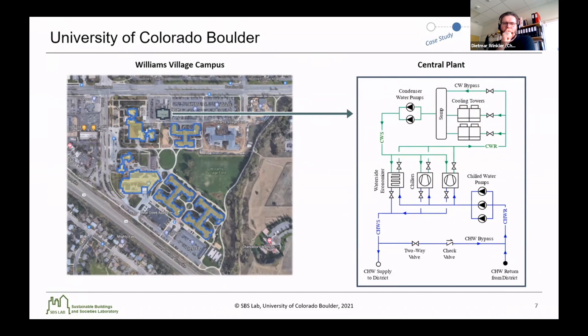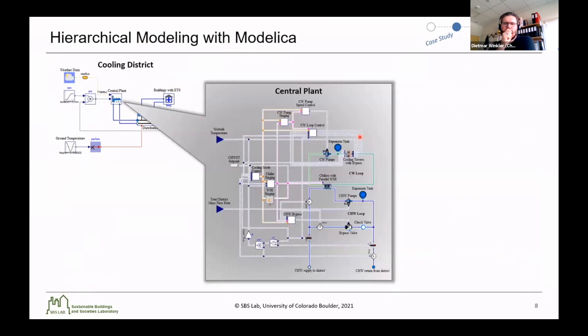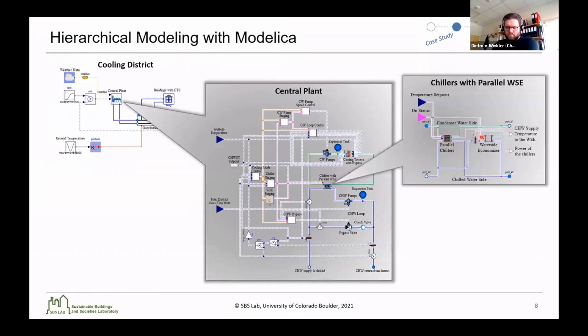This district cooling system was implemented in Modelica. The top-level Modelica diagram shows the model was built hierarchically, allowing each subsystem and building to be tested in isolation and various configurations to be tested as well. At this top level, we have a central plant, a distribution network, and a vectorized set of buildings representing each of the six buildings. Unpacking the central plant, you can see the schematic of the fluid loops with both the condenser water loops and chilled water loops, following a one-to-one relationship with the schematic shown previously. You can also see the two chillers and the waterside economizer in parallel.